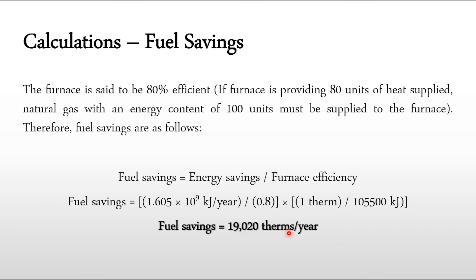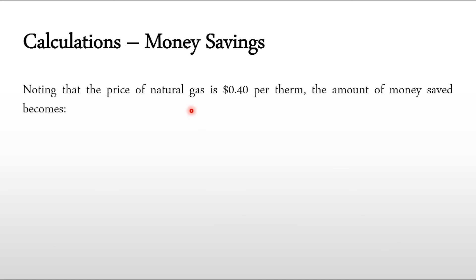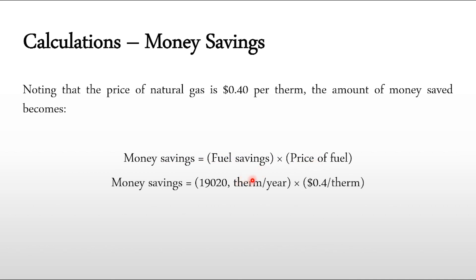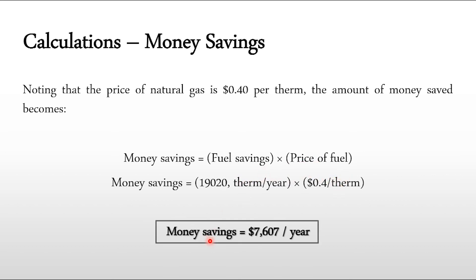That is a significant amount of fuel recovered that was previously wasted. Finally, the money savings: with natural gas priced at $0.4 per therm, money savings = fuel savings × price of fuel = 19,020 therms/yr × $0.4/therm. The therms cancel and we get a money saving of $7,607 per year.